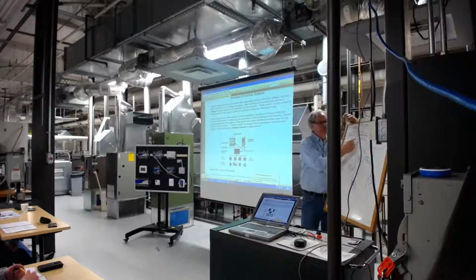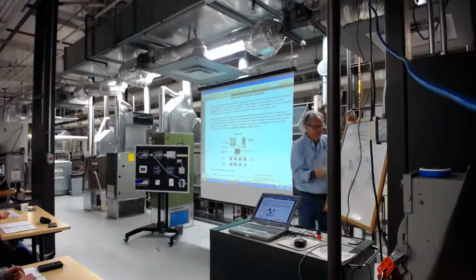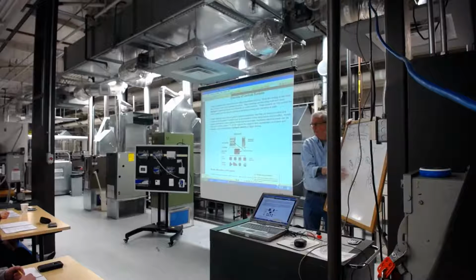The way I really think about it is, yes, there's some high level features. These are also data collectors. Okay. But remember, the whole object of the game is I want a window into my system in real time, right? That's what you want to do. The idea is you're sitting here and saying, okay, maybe this is page 2. And this thing is controlling air handling unit 2. You're saying, I want the discharge air of air handling unit 2. You request it. This thing says, oh, I'll go get it. Comes down, picks up the data, sends it back to you. That's simple. You're just moving data around.